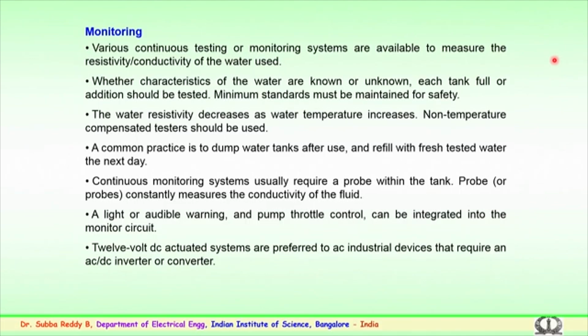The water resistivity decreases as the water temperature increases. So, non-temperature compensated testers should be used for checking this resistivity, because water which is stored for a long period of time could change in resistivity, and it has to be tested before it is applied. A common practice is to dump the water tanks after use and refill with fresh tested water the next day or the next cleaning operation. The water which is left should not be used again and again, so that there is no change in the resistivity of the water because of contamination.